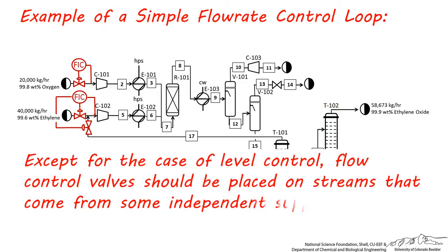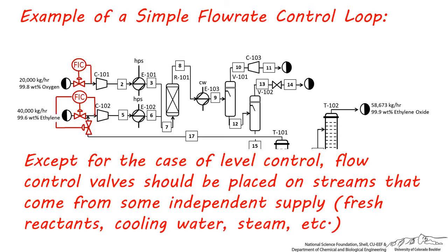Except for the case of level control, flow control valves should be placed on streams that come from some independent supply, such as fresh feed or utility, such as cooling water or steam. Always make sure that flow is controlled by using a supply that can be increased or decreased independently. If you must put a control valve on a process stream, try to make sure it's at the very beginning or end of the process, or it's on a vessel controlling liquid level.